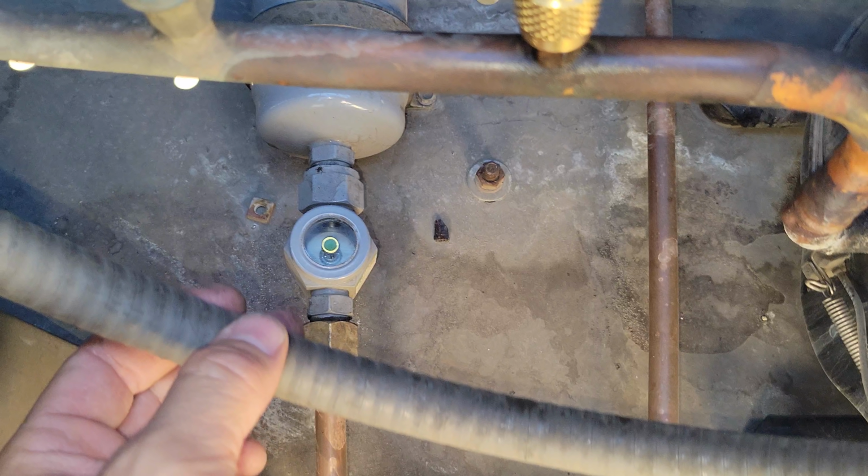If you have a refrigeration system with an expansion valve and a receiver, you need to have a solid column of liquid going to your expansion valve at all times. But it's also important to understand when a clear sight glass can and needs to happen. If you have a severely iced up evaporator coil, you do not want to pay attention to the sight glass until you get all the ice cleared. The system needs to be operating properly and then have a clear sight glass. It's very important to understand that.